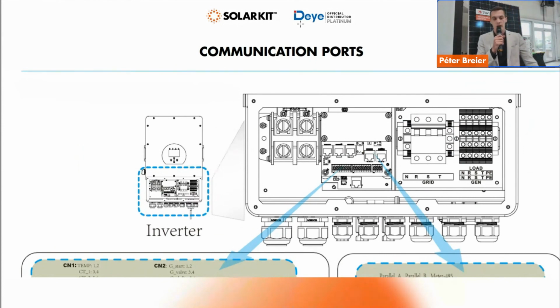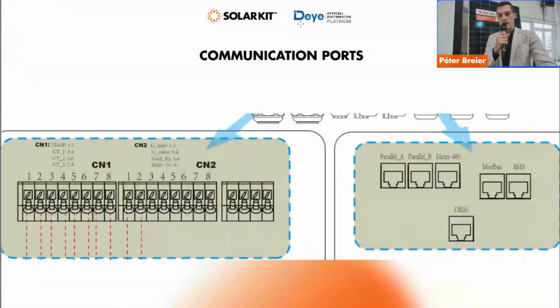So about the communication port, you can see that we are still in the bottom part where we open the inverter, and there are 6 connection terminals. BMS is the one where you want to connect the PCS output of a battery. It's very important that on their batteries, there is an input, an output, and a PCS port. In and out are used for parallel and series connection of the batteries, and only the PCS port is used to connect with the inverter. So you connect the battery PCS port or the control box PCS port to the BMS port on the inverter.